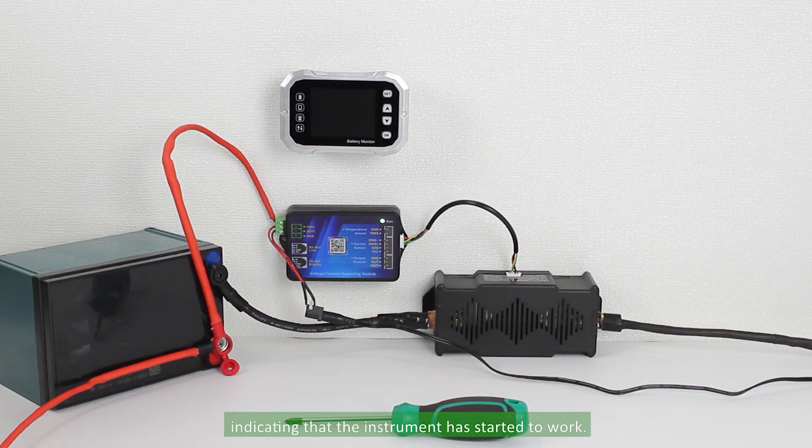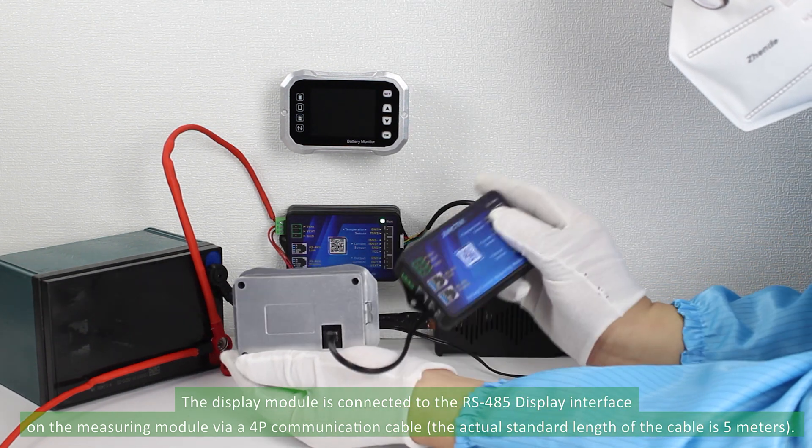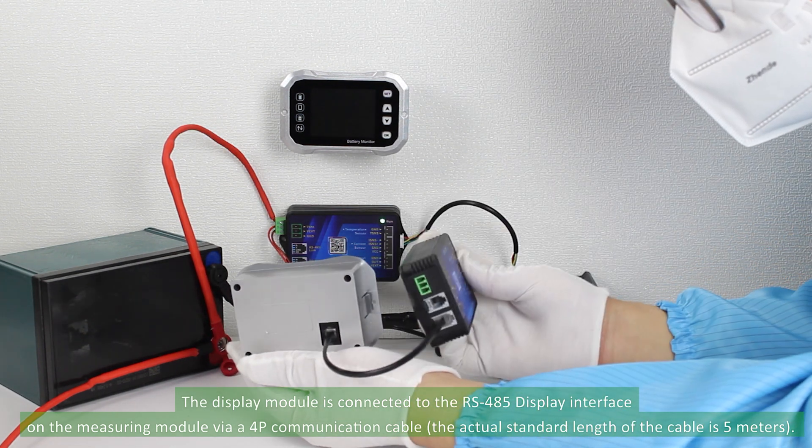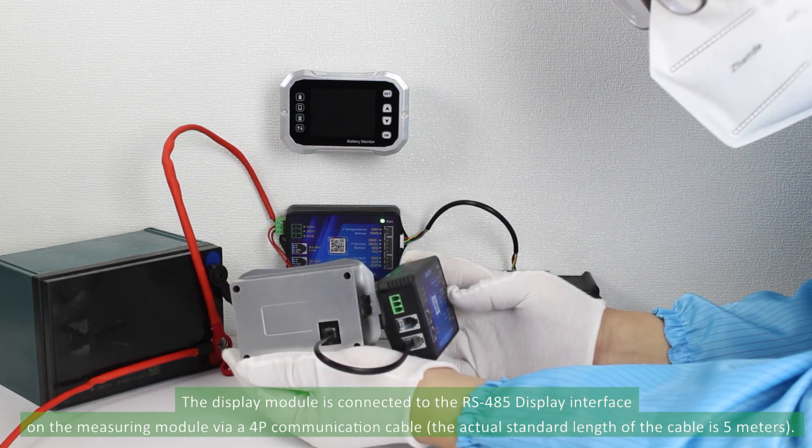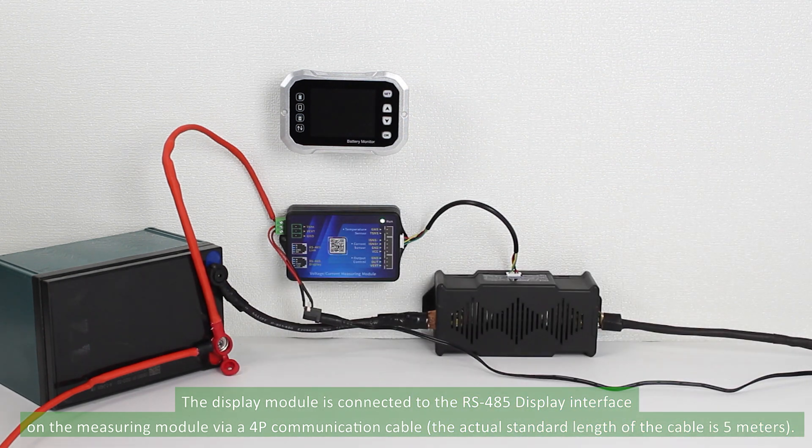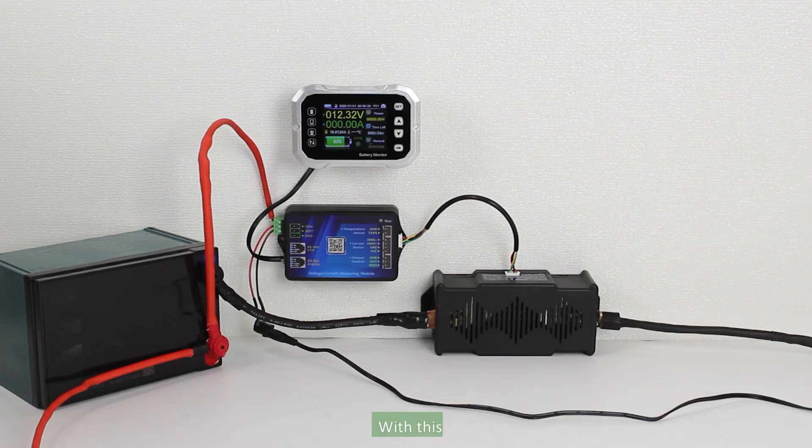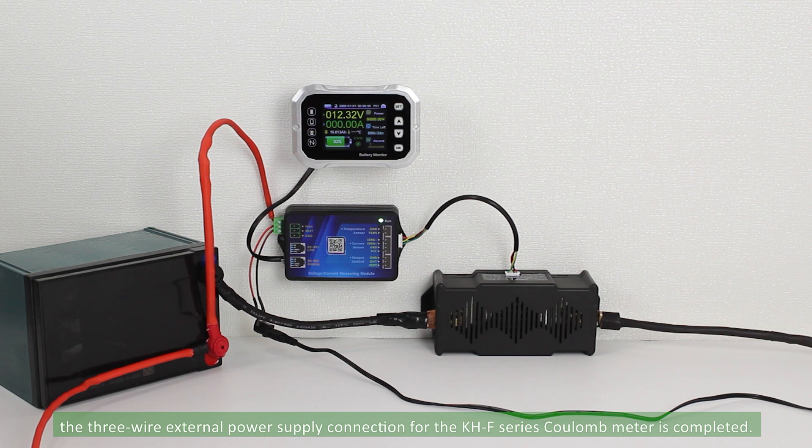The display module is connected to the RS485 display interface on the measuring module via a 4P communication cable. The actual standard length of the cable is 5 meters. With this, the three-wire external power supply connection for the KHF series Coulomb meter is completed.